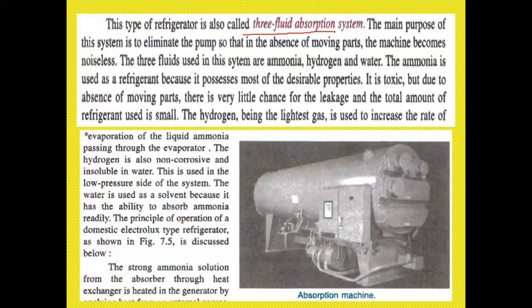The main purpose of this system is to eliminate the pump, so that in the absence of the pump, a moving part, the machine becomes noiseless. When we remove the pump, automatically the machine becomes noiseless. Therefore, this machine is a noiseless machine. The three fluids used in this system are ammonia, hydrogen, and water. That's why it is given the name three fluid system: ammonia, hydrogen, and water.